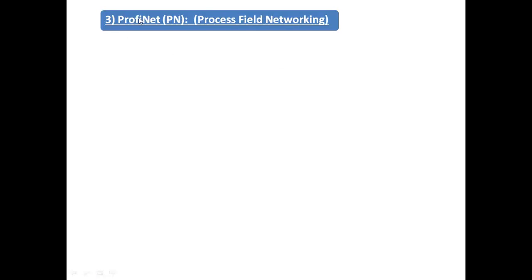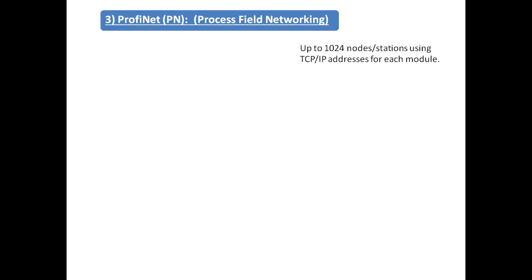Next is Profinet — also known as PN. If you expand this, it stands for Process Field Network. It supports 1024 nodes or stations, using TCP/IP addresses for each module. Each module should have a unique IP address — like internet addresses starting from 192.168.0.1, and so on. Different brands have their own IP address starting formats.